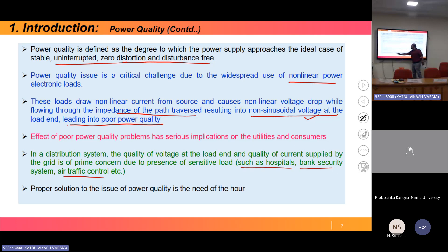Then how to improve power quality? Power quality here means both current quality and voltage quality. For current quality improvement, one active filter is responsible. For voltage quality improvement, another filter is responsible. The series active power filter is responsible for improving voltage-related qualities: voltage sag, voltage swell, voltage harmonics. Similarly, the shunt active power filter handles current harmonics, unbalance in current, regulation of DC link voltage, and reactive power compensation. If you are least bothered about voltage quality and want only current quality improvement, then better to go for the shunt APF.